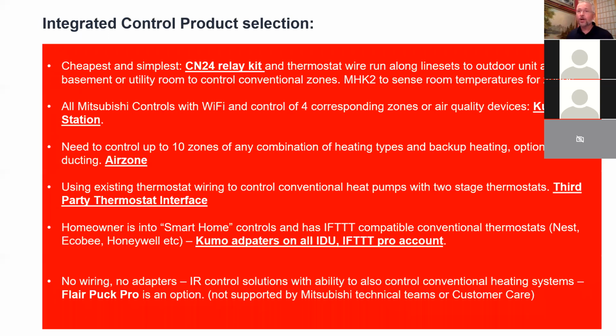The cheapest and simplest way to accomplish integrated controls is probably the CN24 relay kit. A lot of guys don't gravitate towards that because it seems like running wires is troublesome or whatever, but it's pretty bulletproof and low tech. The Kumo station has been used extensively in Massachusetts. There's hundreds upon hundreds of these systems out there, and people have gotten pretty good at using them. It's pretty nice to be able to manipulate all the controls on your phone. It's a good client feature, and if you're sizing the system to 100%, the frequency that it's going to turn on the backup is pretty low, and so people get an additional benefit that's paid for through the New York program to have integrated controls and manipulate that.